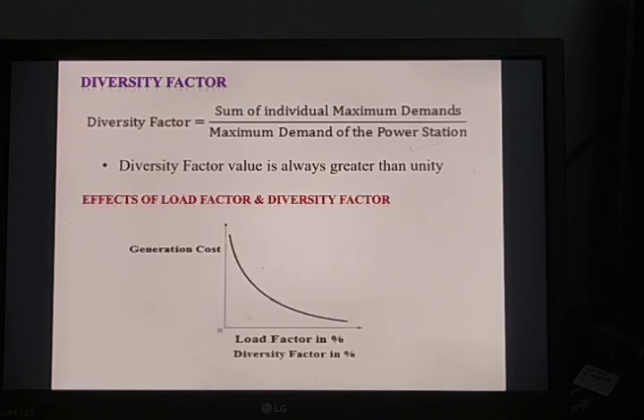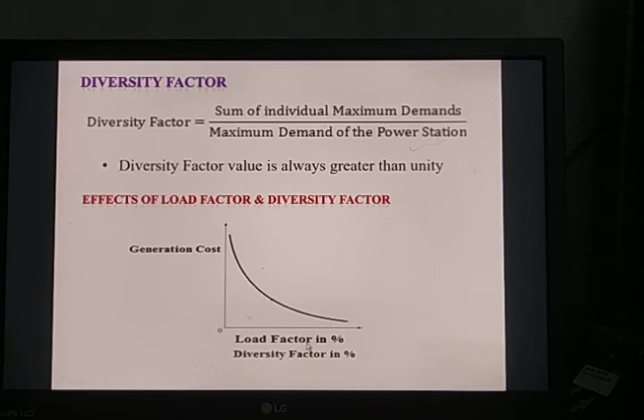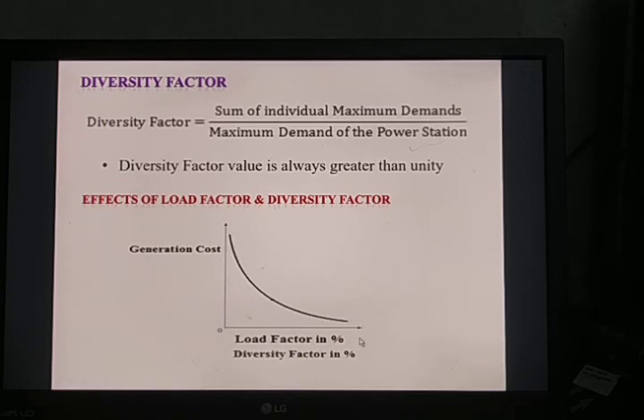Load factor and diversity factor play an important role in deciding the cost of electrical energy. Different types of consumers — domestic, industrial, commercial — are charged different tariffs. The cost is fixed with the help of load factor and diversity factor. The graph shows x-axis as load factor and diversity factor, and y-axis as generation cost. If the values of load factor and diversity factor are higher, the overall per-unit cost of generation will be lower.